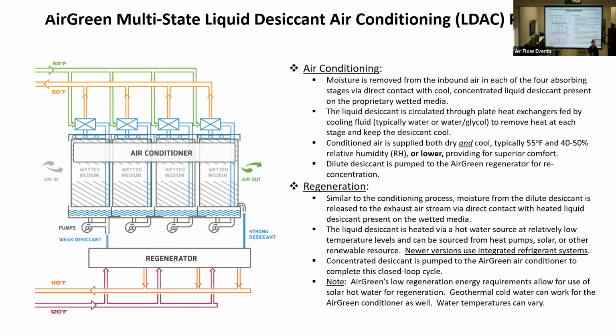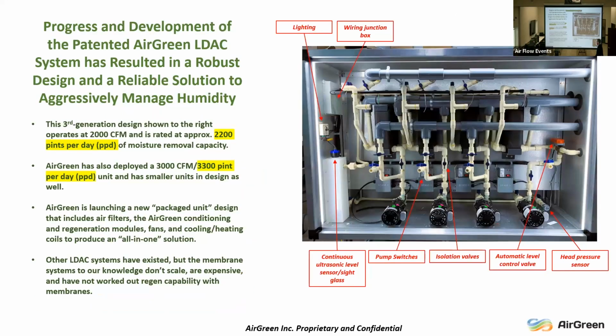Since then, we've had separate chilled water coils, and in some cases, in larger applications, a separate chilled water air handler in parallel, so that we can send our chilled water to where it needs to be to completely separate the temperature control and humidity control. So your basic design has a wetted media and heat exchange, and you don't really care where your sources are coming from, the cooling source, the heating source, the regenerator and the air conditioner source. It just makes it fit more applications.